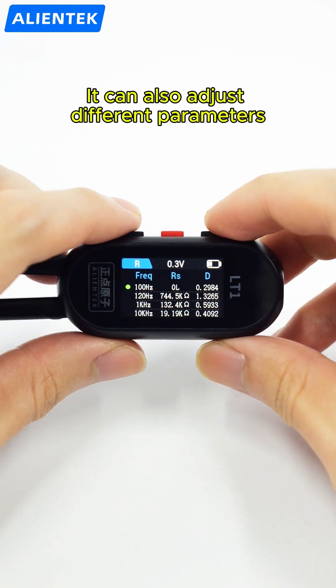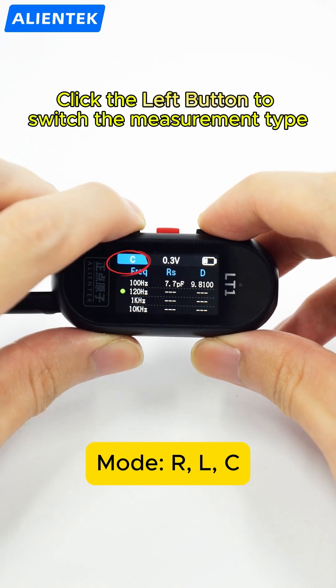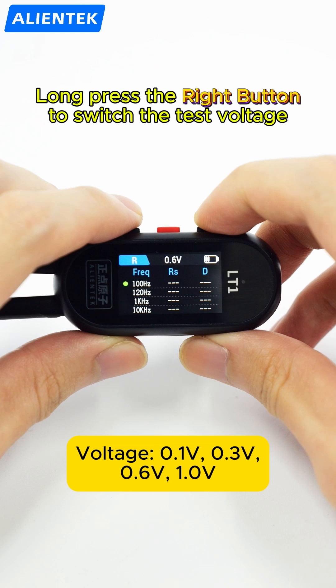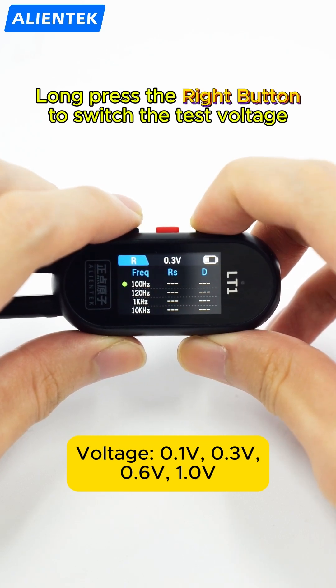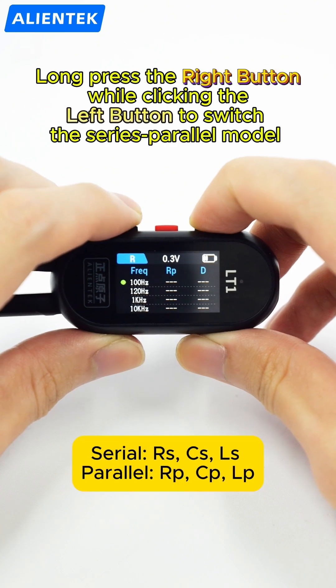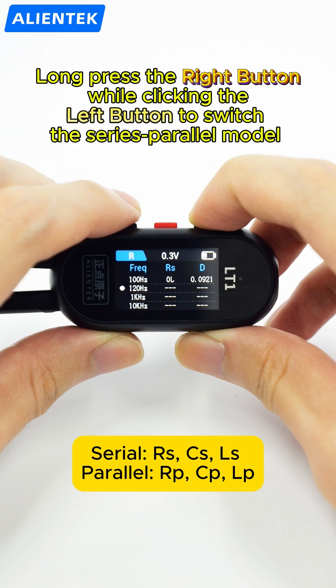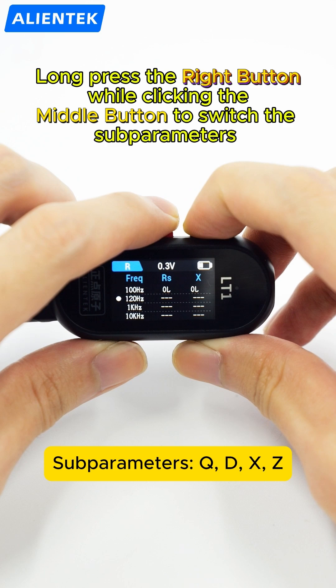It can also adjust different parameters. Click the left button to switch the measurement type. Long press the right button to switch the test voltage. Long press the right button while clicking the left button to switch the series/parallel model. Long press the right button while clicking the middle button to switch the subparameters.